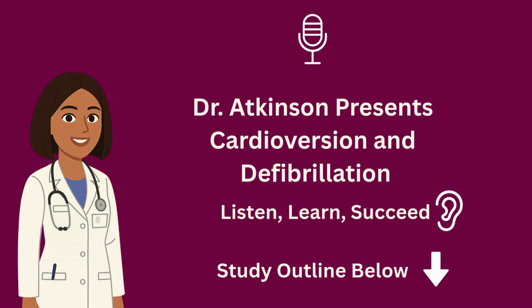The key difference is timing. Cardioversion is synchronized with the QRS complex on the ECG. It waits until ventricular depolarization to deliver the shock. Defibrillation, on the other hand, is unsynchronized and delivered immediately. Both use the same device, a defibrillator, but the voltage required for defibrillation is higher and can cause more myocardial damage. Modern devices are biphasic, which means the current flows in two directions and then back, making the shocks more efficient and requiring less energy than older monophasic models.